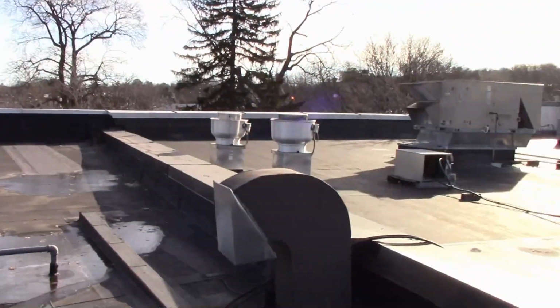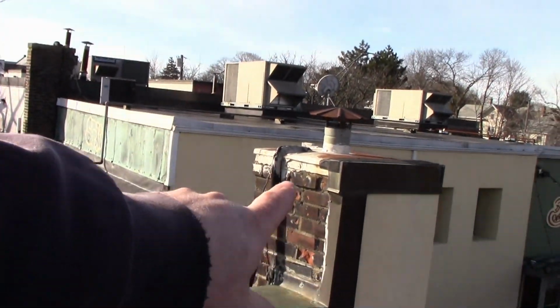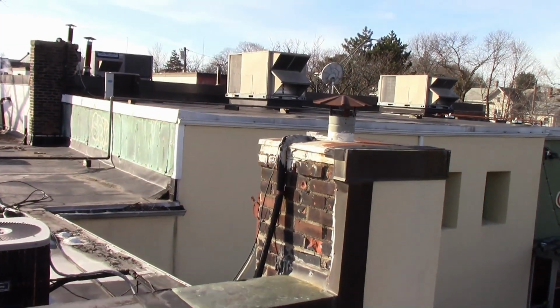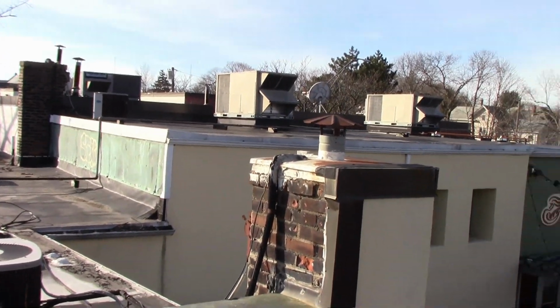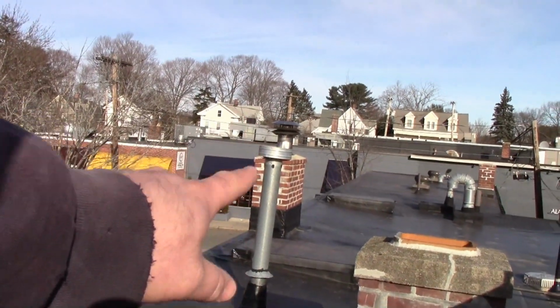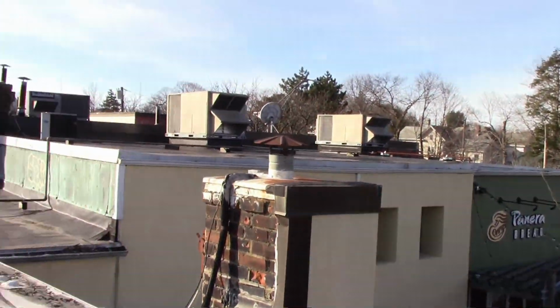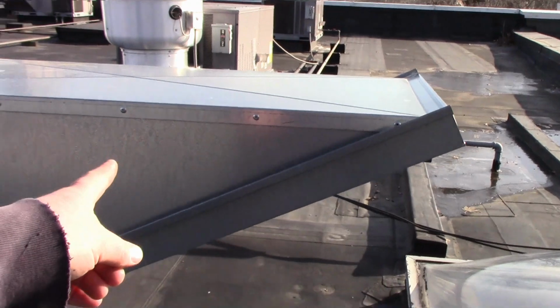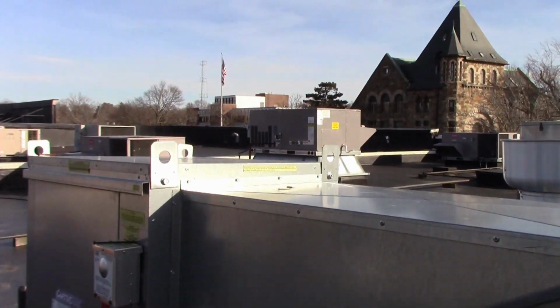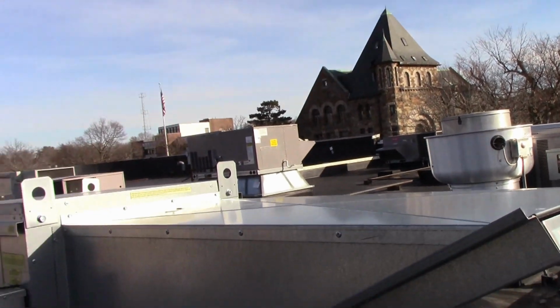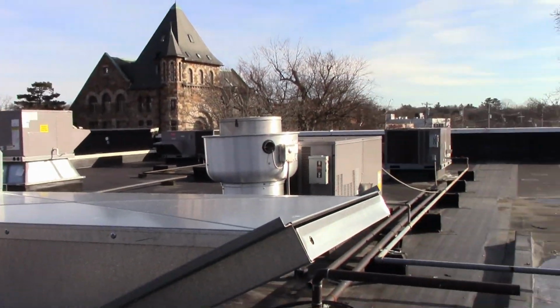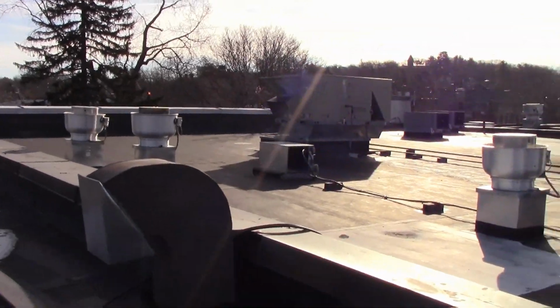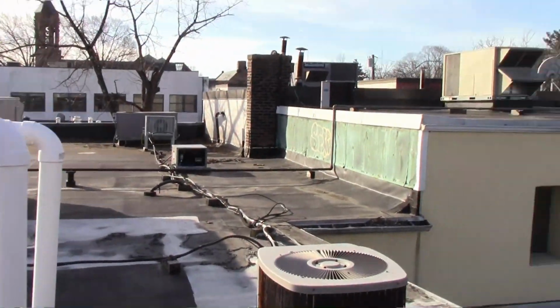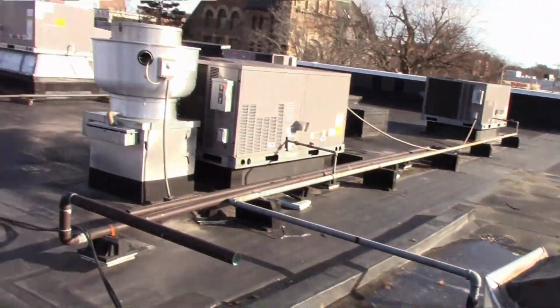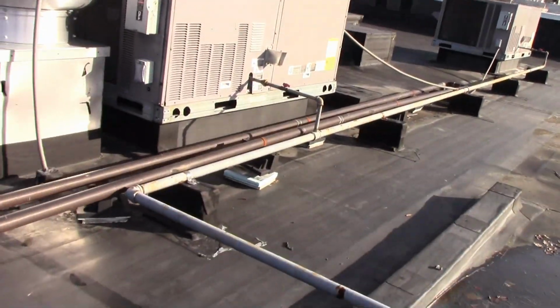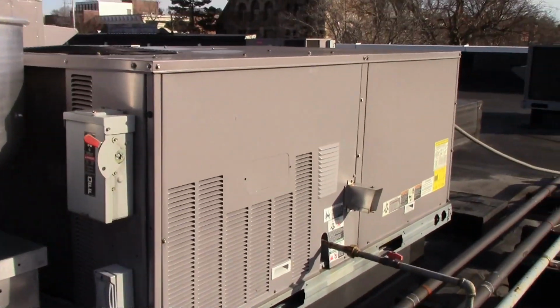If I don't, I might not. So there is a hot water tank, which I'm assuming that one is theirs. Either that one or that one. Probably doesn't have a powered vent exhaust. So if I do shut this off, I have to make sure that the building isn't under too much of a negative draft to let those hot water tanks exhaust. This is part of a little strip mall, so it might not be as critical as if this was a single standalone building, but something I'll have to check. So let's hit the first one.